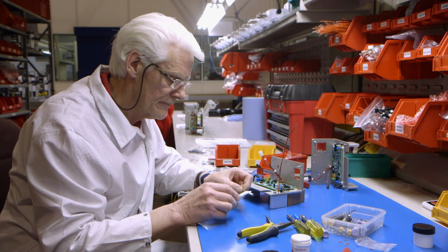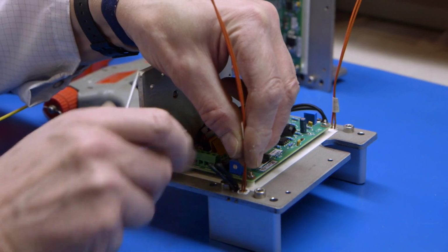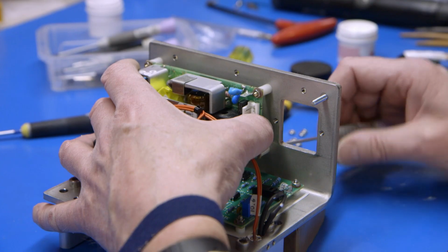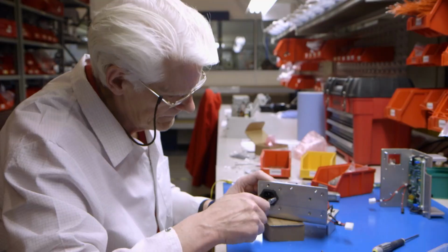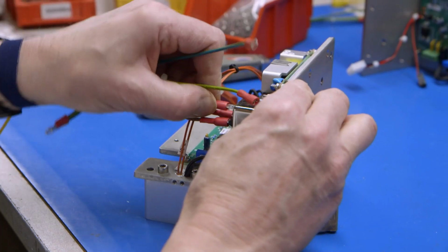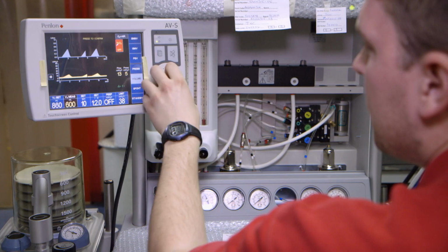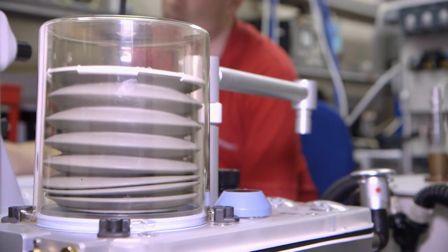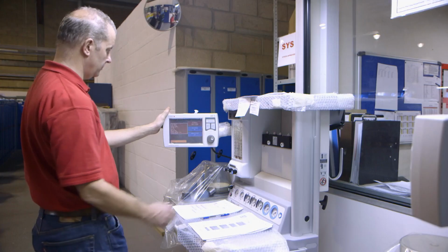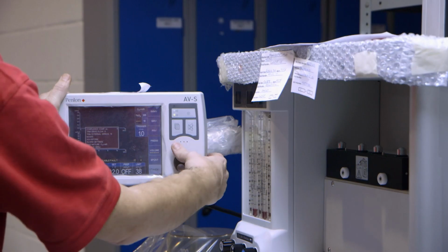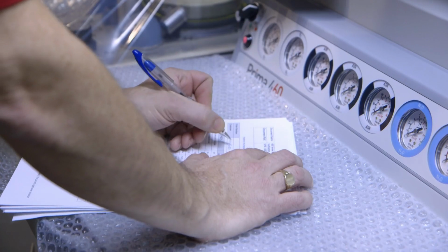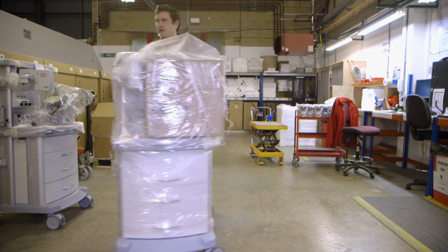Another important element of the anesthetic machine is the absorber, which removes the carbon dioxide from the system. The absorber is assembled with heaters, and the electrical boxes are added and tested. The absorber and ventilator are tested. Displays and monitors are added before further tests. When all the extensive checks have been completed, the anesthetic machines are shipped out to hospitals in more than 100 countries across the world.